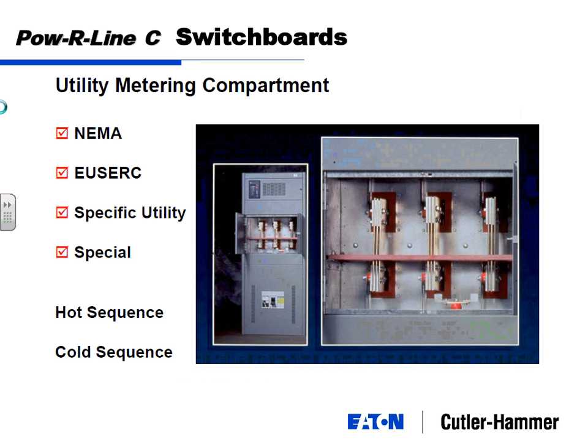We're kind of moving away from this. Xcel used to put metering compartments inside switchboards, inside buildings, and they've moved to the point now where they want those CTs and metering outside. So you'll put the switchboard in, and they're directing more and more that you put a separate set of CTs outside. It's an Xcel thing, so you may see different utilities do different things, and I don't think it's necessarily a rule yet. It's just a guideline that they're pushing.